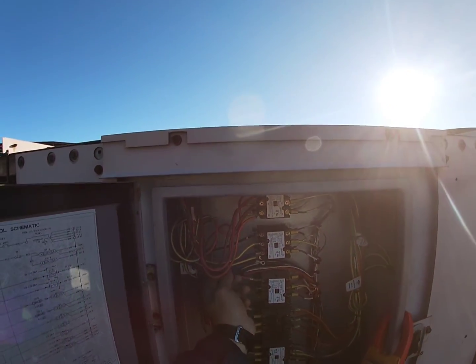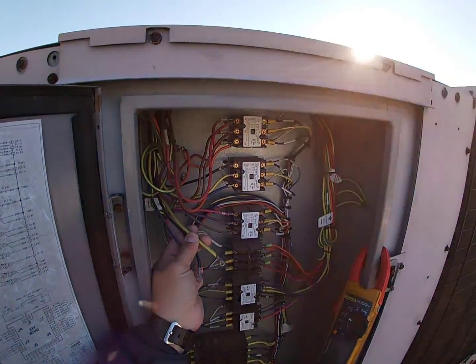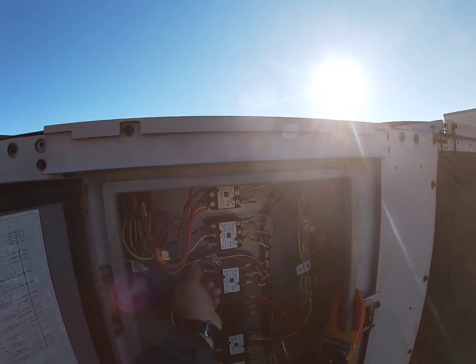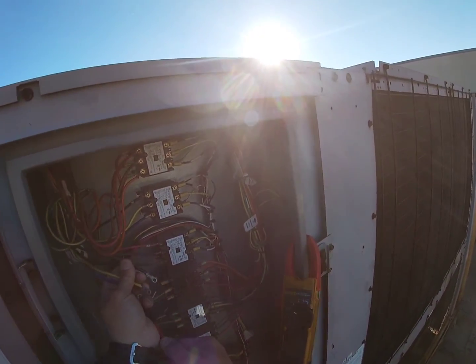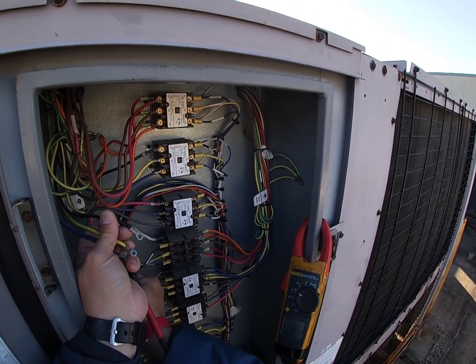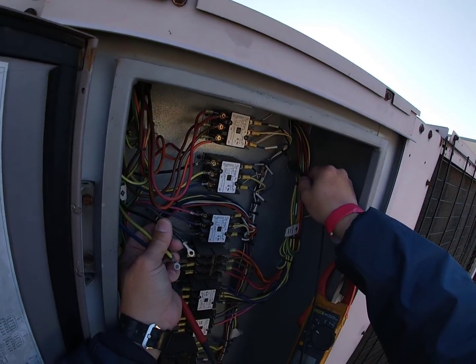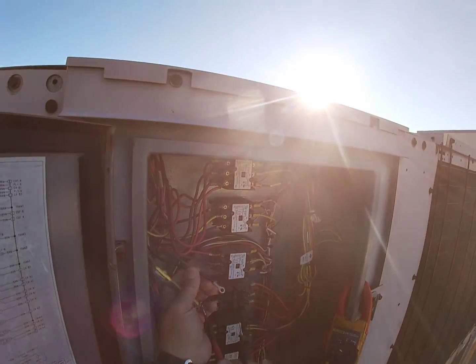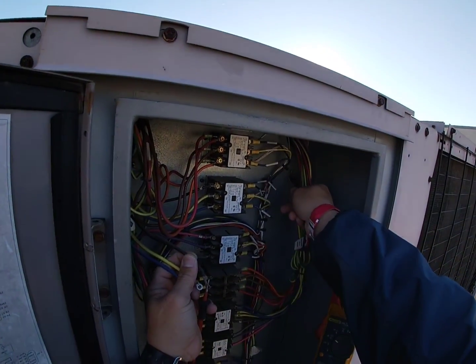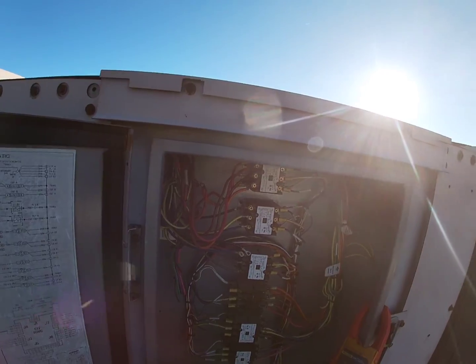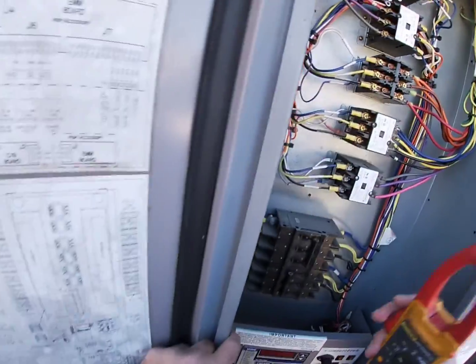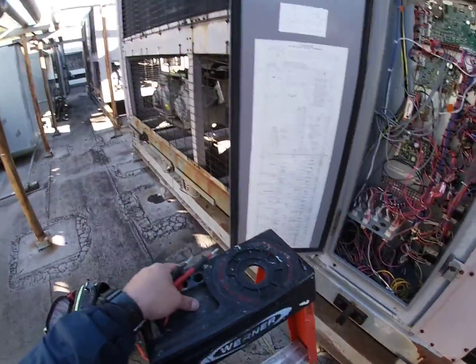So, all right. We know we have a bad condenser fan motor here. We're gonna have to figure out which motor that is, but let's double check it one more time. Go straight to ground. Okay, so yeah, that motor's bad. That leg is bad. Bad. Bad. So this motor's no good. Just for kicks and giggles, we'll go ahead and run the megger and see what it shows, since I have it here with me anyways.